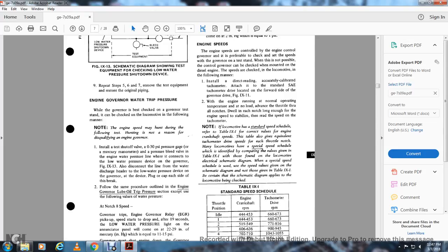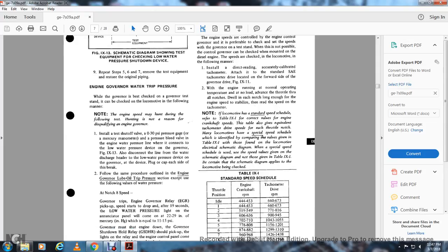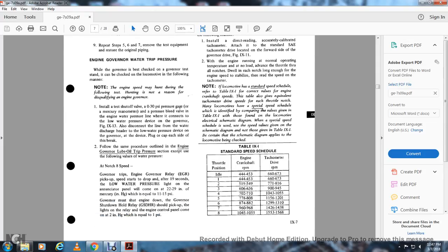Repeat steps 5, 6, and 7, then remove the test equipment and restore the original piping. Engine governor water trip pressure: The governor is best checked on a governor test stand; however, the check can be performed on the locomotive. Note that the engine speed may hunt during the following test; hunting is not a reason for disqualifying the engine governor. Install a test shutoff valve with a 0-to-30 PSI pressure gauge or mercury manometer, and a pressure bleed valve, in the engine water pressure line connected to the low water pressure device on the governor (figure 9-13). Disconnect the water discharge line from the low water pressure device on the governor; plug and cap each side. Follow the same procedure as for the engine governor low oil trip, with the following water pressure values.